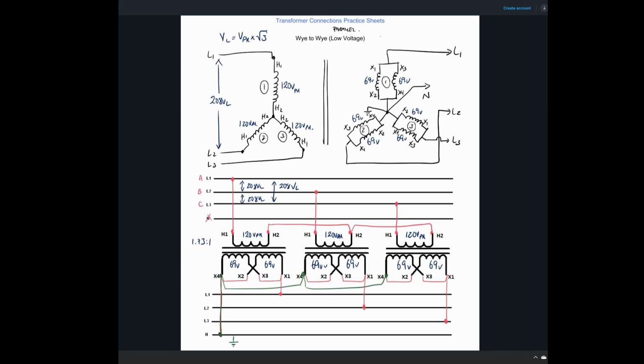Beauty. Okay, so now it's a question of what the voltage is from line to line here. If we have 69 volts from line to neutral, then what do we have from line to line? Well, we would have 69, and then we would multiply that by root 3, and that gives us basically 120 volts out.